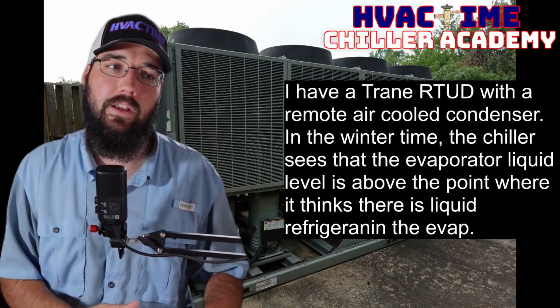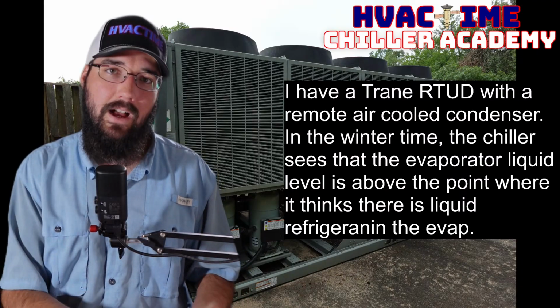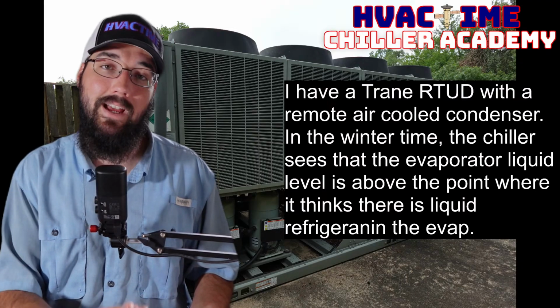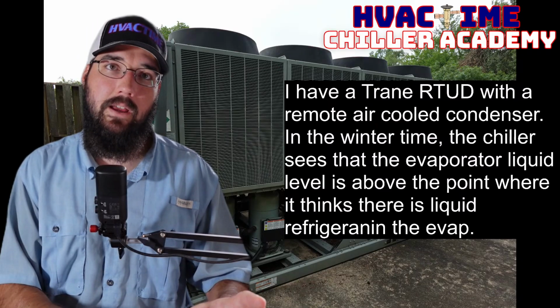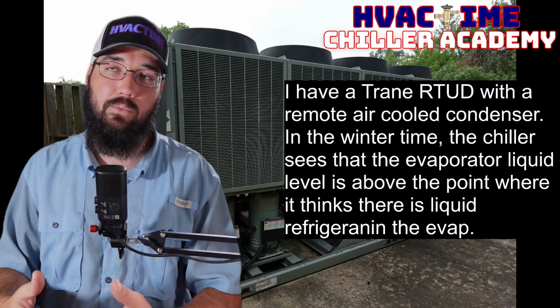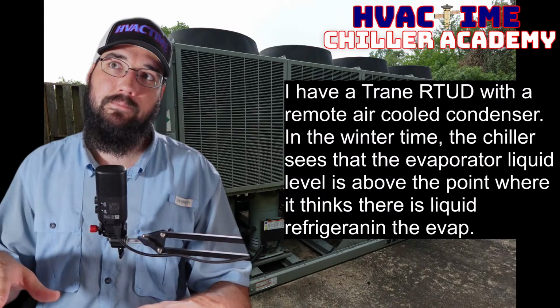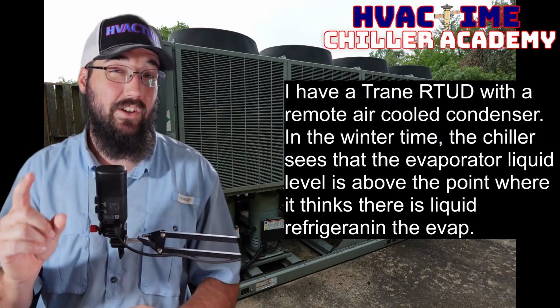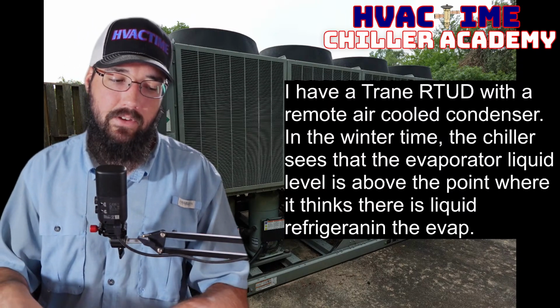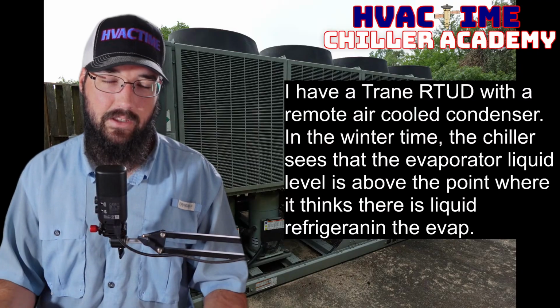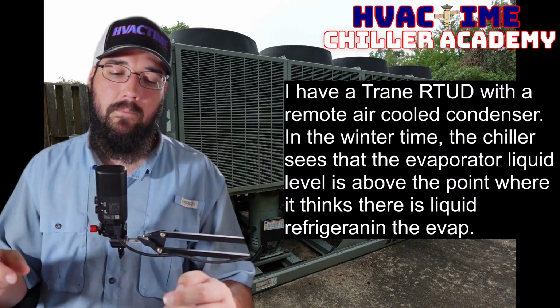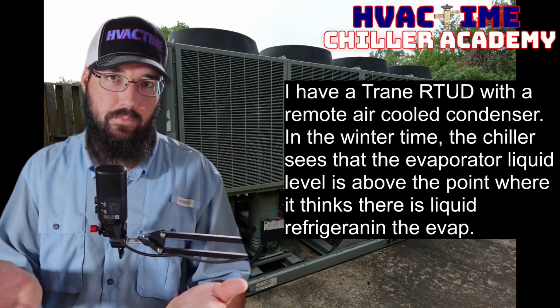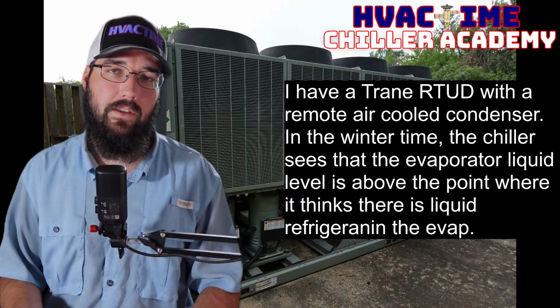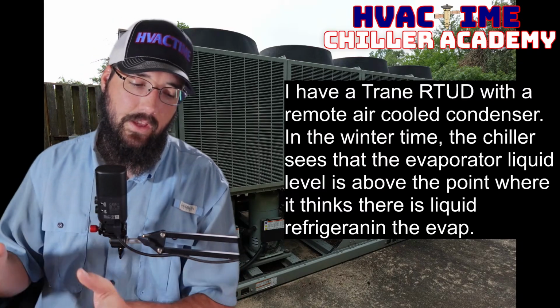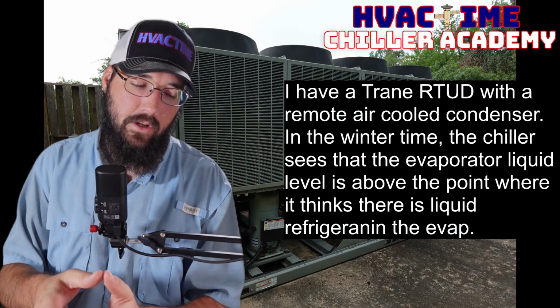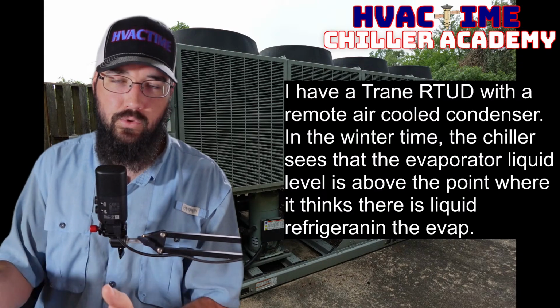making the thought that we are seeing oil and oil foaming causing a higher liquid level being sensed at the point of pump down. So that would be what I'm trying to verify, because yes, I would say that it is likely that could be an oil migration issue. It's also likely, so keep this in mind, that if you're having a heavy oil migration problem and that oil is having trouble stacking in the evaporator and it's not recovering that oil correctly, one reason the liquid level sensor may still be showing level and that it didn't fully pump down is because you hit the pump down set point too quickly due to the heavy oil charge.